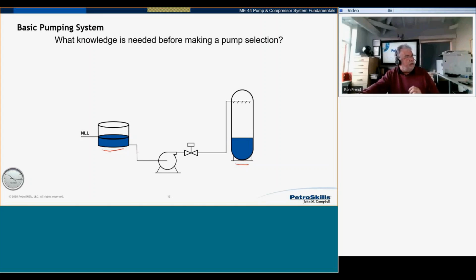The first thing we do is say, well, this is a system. I've got my system, and I split it into two halves. I could put a line in the middle, and I could look at the suction side and the discharge side. Because remember, the total dynamic head is the head on the discharge minus the head on the suction. If I know the total amount of energy, I then need to figure out the total amount of power. Okay, so what do I need? I need to know how much energy I have to put in, and I want that in terms of head. So let's think of old Bernoulli. Remember Bernoulli when you went to college? Well, here he is again.